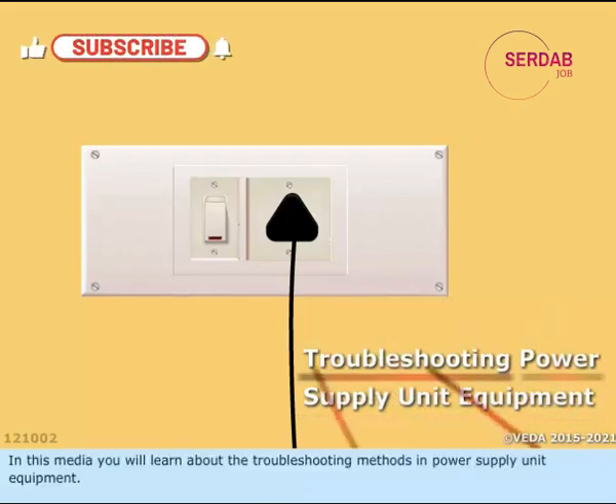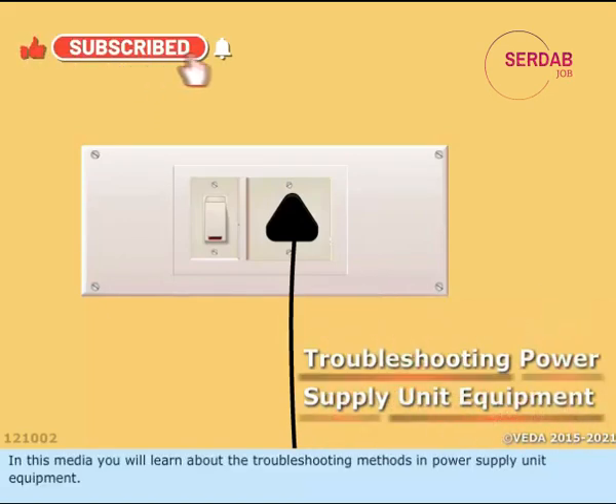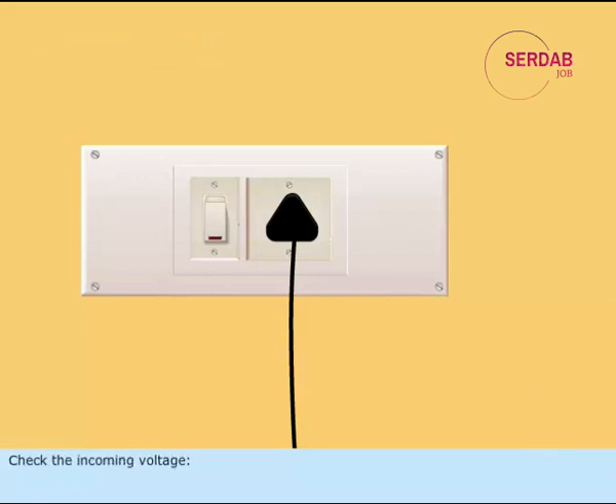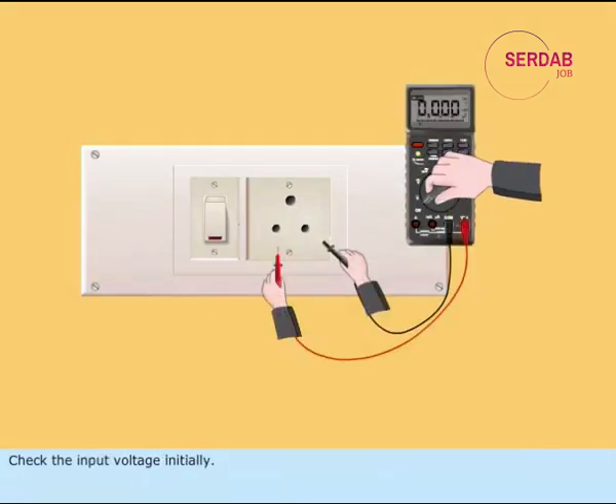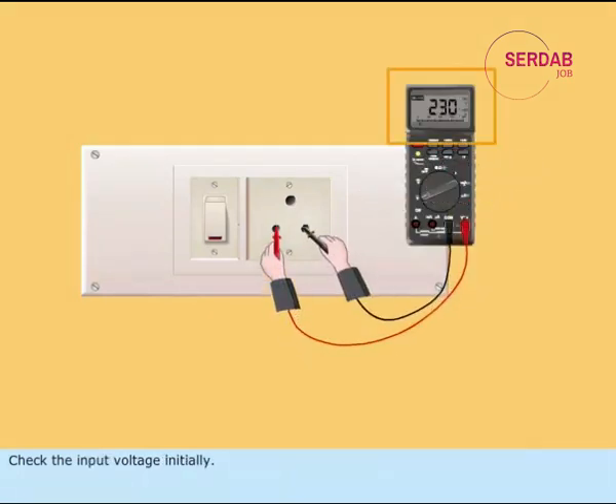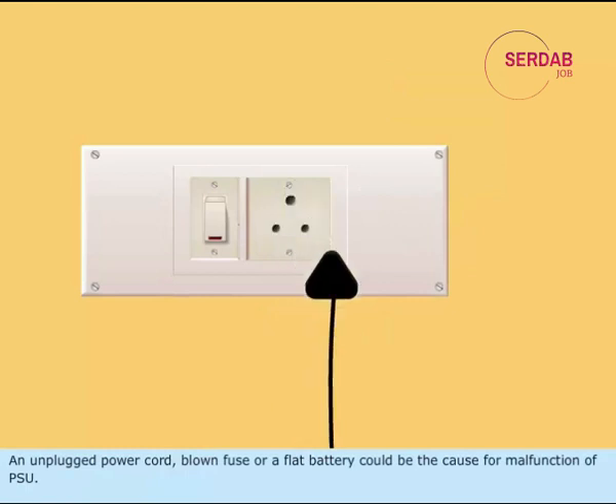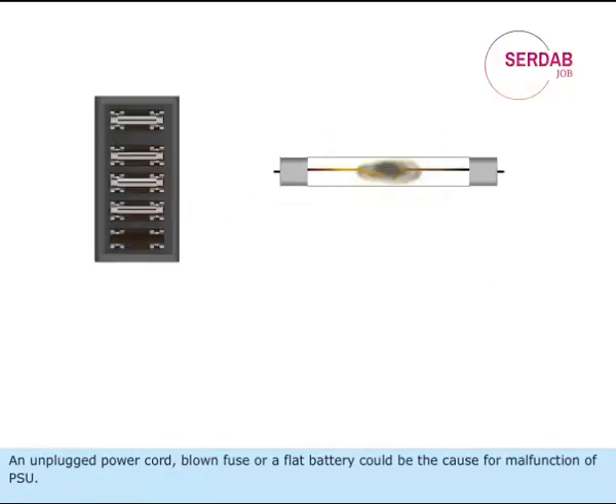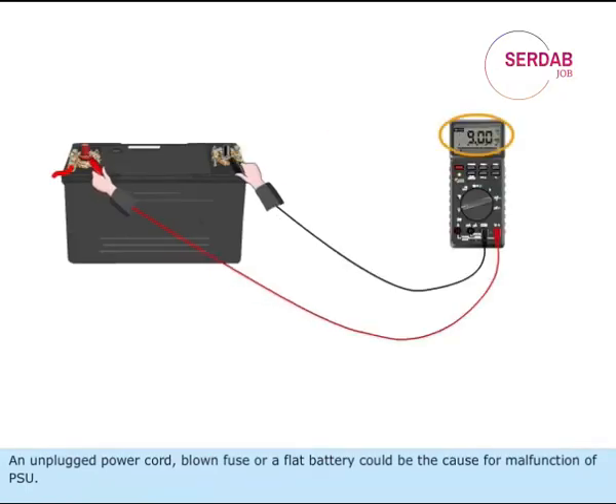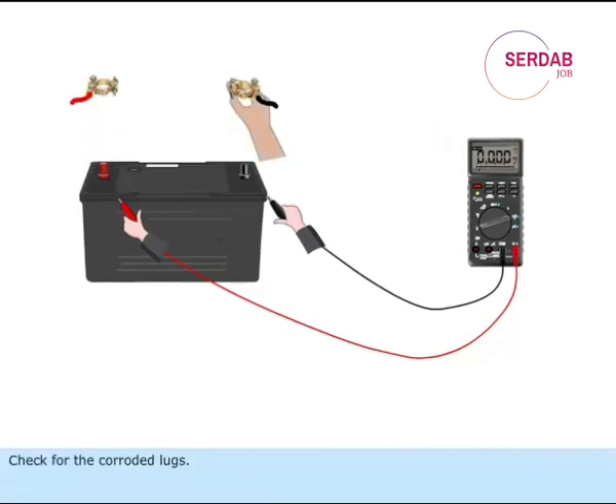In this media, you will learn about the troubleshooting methods in power supply unit equipment. Check the incoming voltage. Check the input voltage initially. An unplugged power cord, blown fuse, or a flat battery could be the cause for malfunction of PSU. Check for the corroded lugs. Clean the battery terminals and lugs.